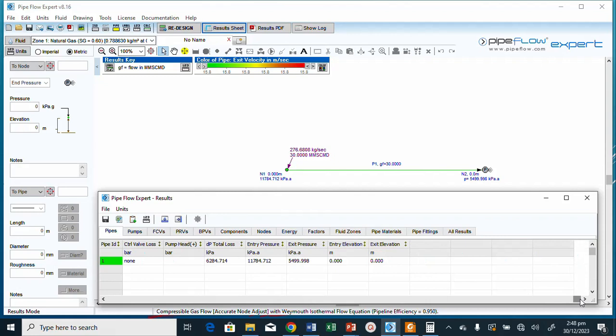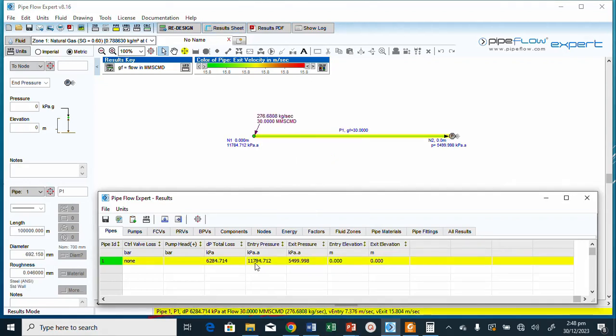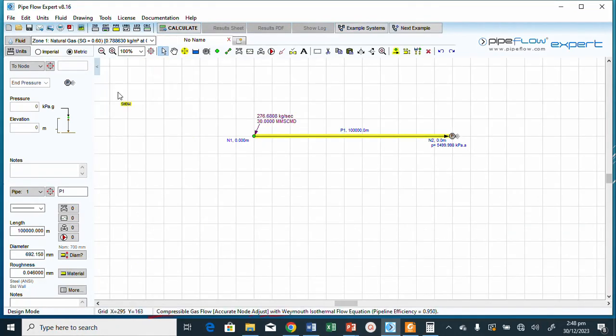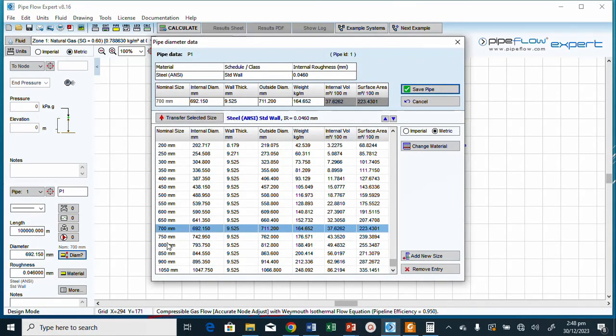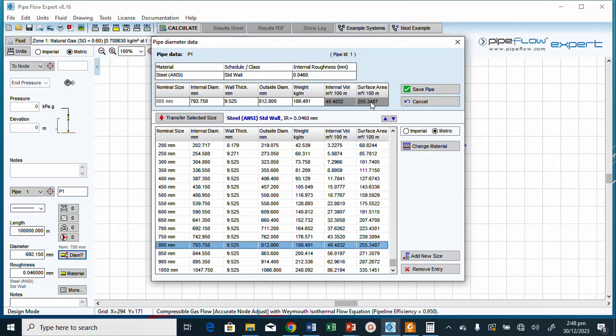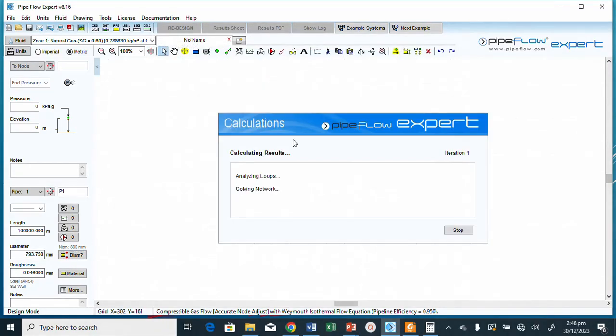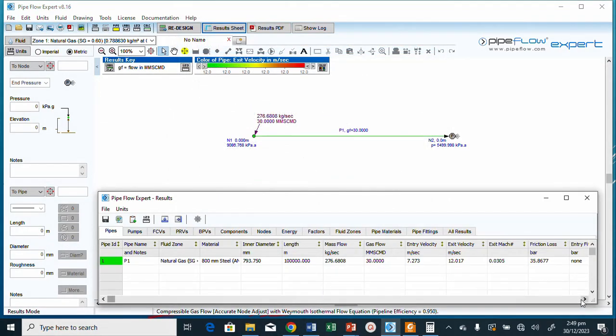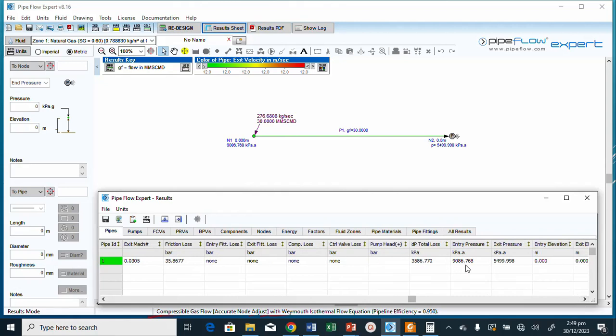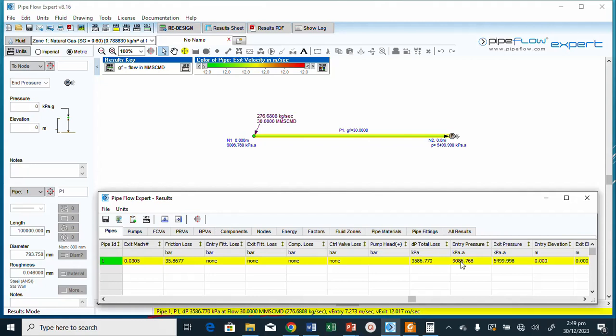After calculating with 700 mm, the entry pressure is now 11,784 kPa — still too high. We need to reduce it further, so let's try 800 mm.